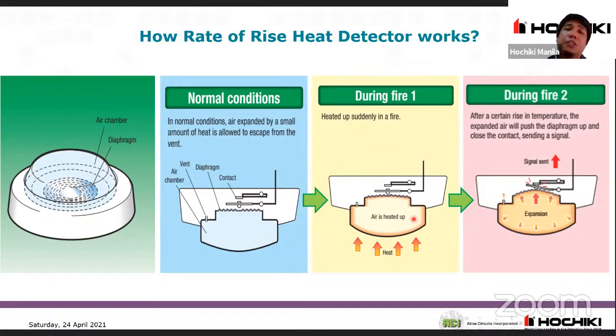For your information, for the rate of rise, the activation based on NFPA is 15 degrees Fahrenheit in less than 1 minute. When there's a change in temperature of 15 degrees Fahrenheit in less than 1 minute, the heat detector will activate.